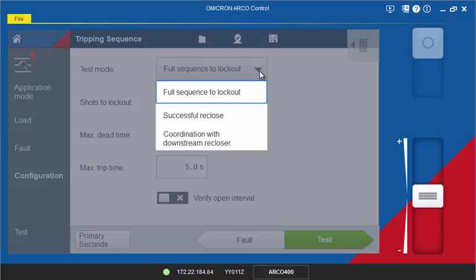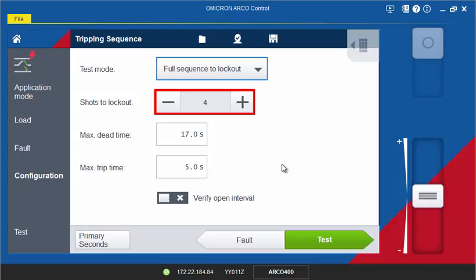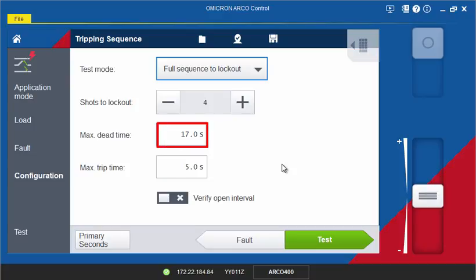If you are testing the full sequence to lockout, define the number of shots to lockout according to the settings in the controller. For the trip sequence test, timeout values must be defined in order to abort the test sequence if the signals that are expected do not occur within defined parameters. Enter the maximum dead time, which has to be a larger duration than the longest expected open interval time of the controller.